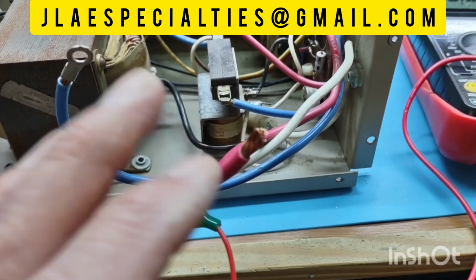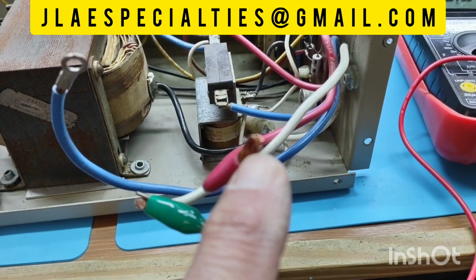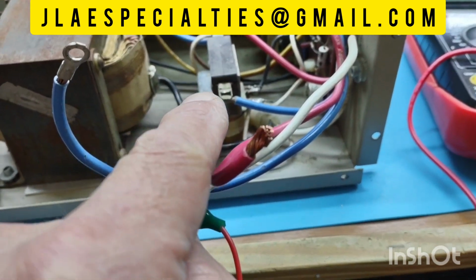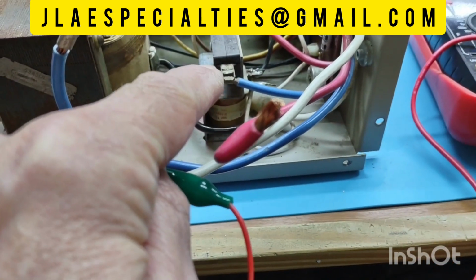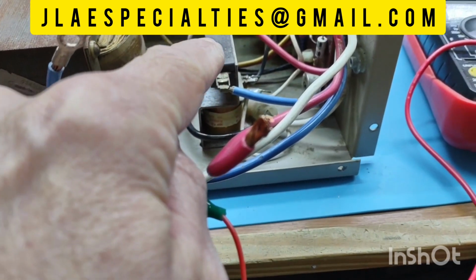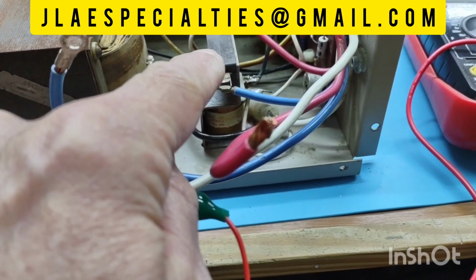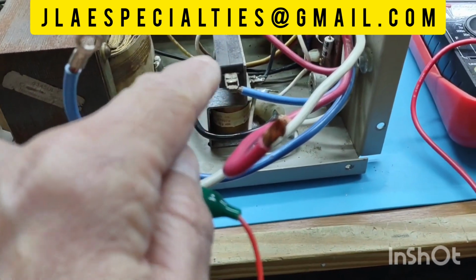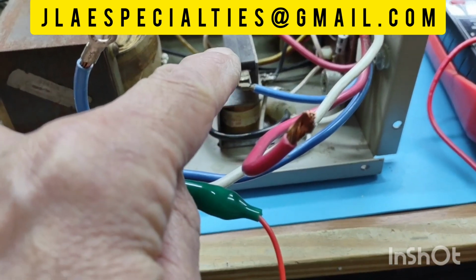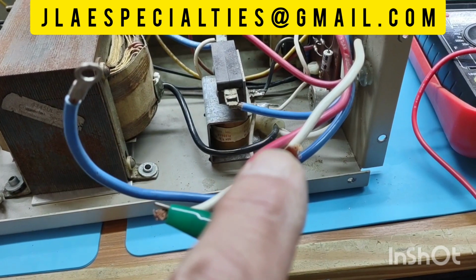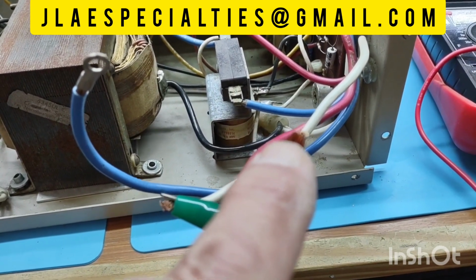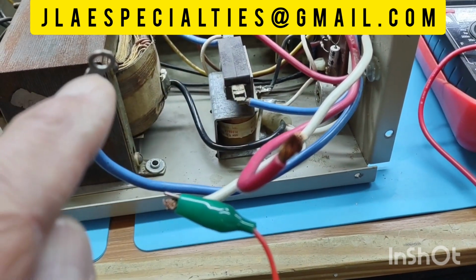So when the unit's turned off, battery feeds through the unit through that contactor relay right there. That relay is closed when there's no power applied -- in other words, house power or shore power. So you're feeding your battery voltage through the red wire, and that battery voltage comes back out on the blue wire.